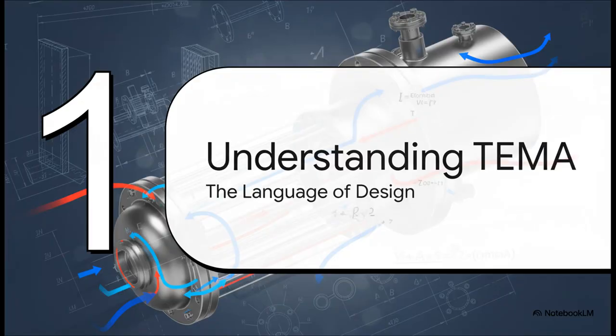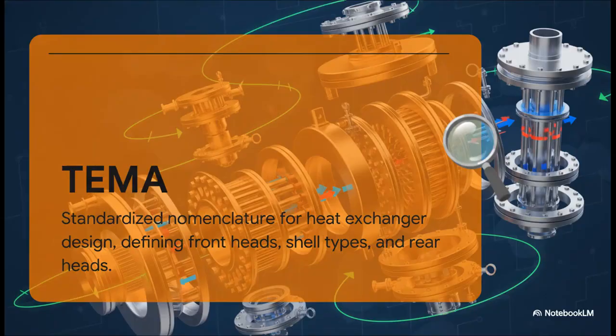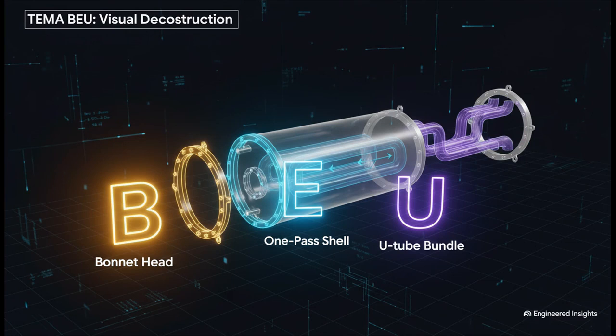First things first, we have to speak the language. And when it comes to heat exchangers, that language is all defined by the Tubular Exchanger Manufacturers Association, or as everyone calls it, TEMA. What TEMA gives us is this simple but incredibly powerful system, a three-letter code that spells out the exact mechanical build of an exchanger. And this isn't just for convenience, it's a universal language. It means an engineer in Houston can specify a BEU type, and a fabricator halfway across the world in Singapore knows exactly what they need to build. No confusion, no mistakes.